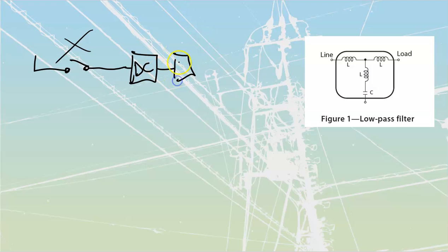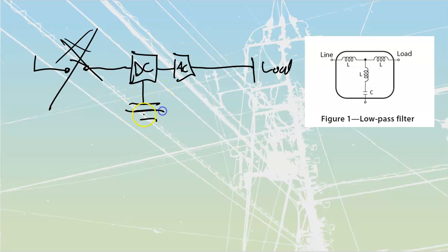DC, and then I'm going to convert this back into synthetic AC on the output, and that DC is going to be fed out into a battery. So that DC is just pulling out to, once again, here's all of my loads at this end over here, but it's going directly through this. So it's always going to be online. If this would fail out here, once again, then the battery that I have, that's supposed to be a battery, we'll just make it more battery looking, will immediately come back on because it's always going to be connected to the system through that inverter as we head this thing back out.